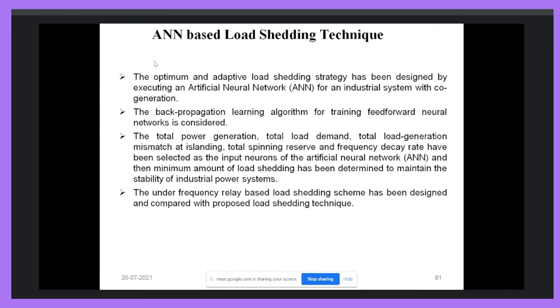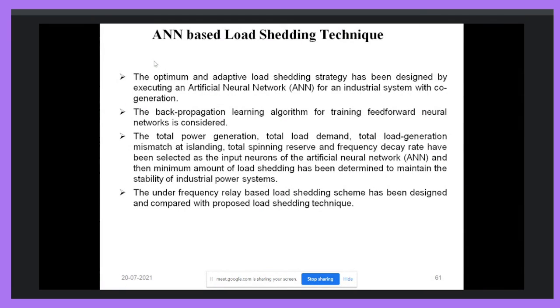Which parameters between output and input are very strongly related to the output? Here the output is the load shedding amount. So what parameters are related to the load shedding amount that we have to give as input to the artificial neural network? Here we have considered total power generation, total load demand, total load generation mismatch at islanding, total spinning reserve, and frequency decay rate. These are the parameters considered as input to the neural network. And the output, the minimum amount of load shedding determined for the particular operating condition, is considered as the output of the ANN.